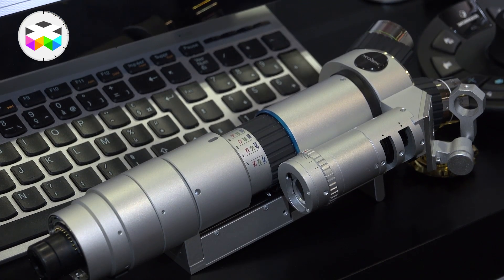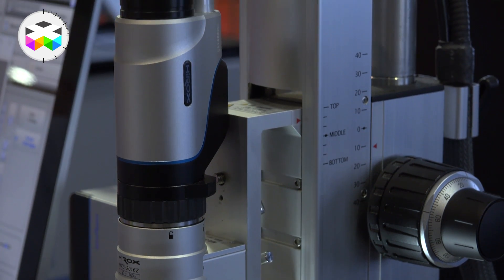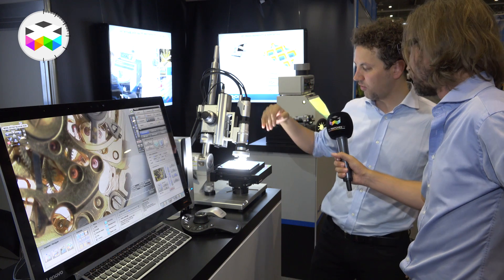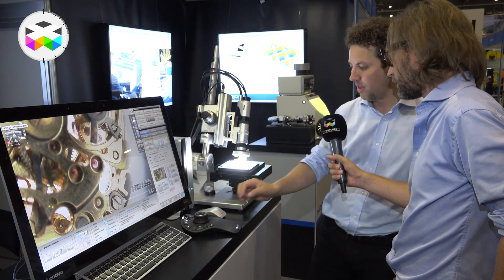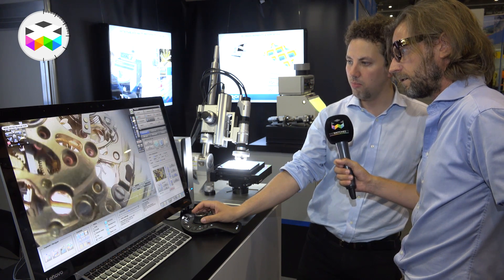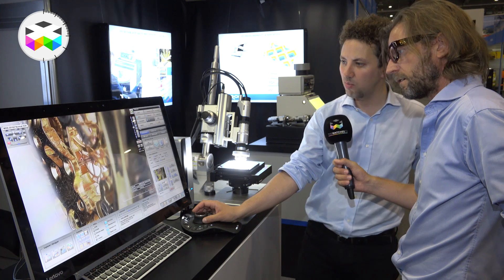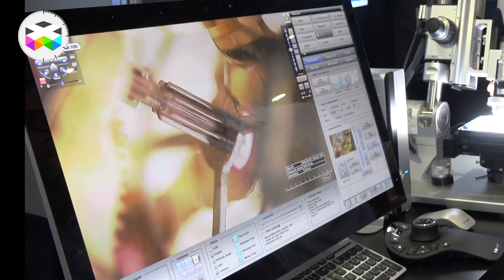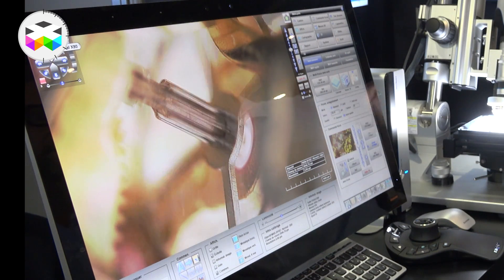Now let's have fun and go for a demo. Right now we have a lens with magnification from 20 up to 160 times. We have the possibility to tilt the level of inspection, and on top of tilting we have a system of rotational mirrors, which allows motorized rotation to look at hidden places. Right now we can see inside the movements and look at specific details that are usually very hard to reach. We can see a little impurity inside the movement.